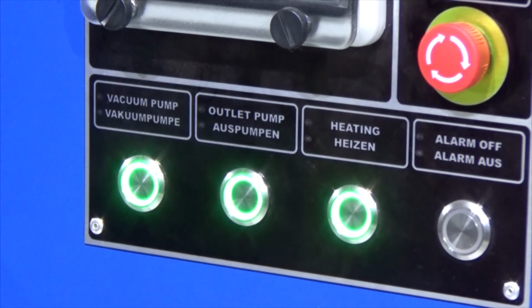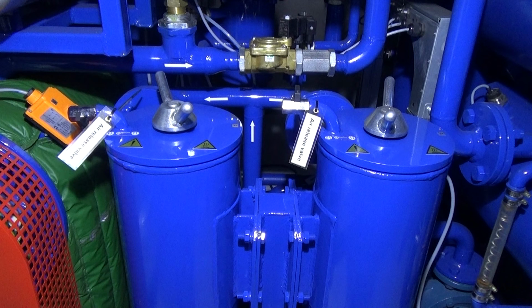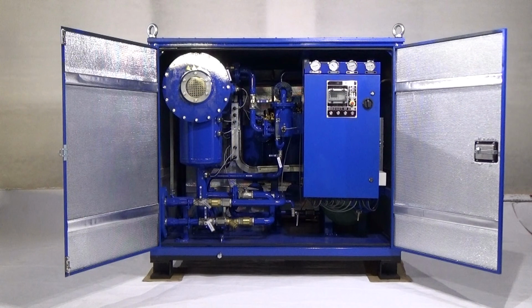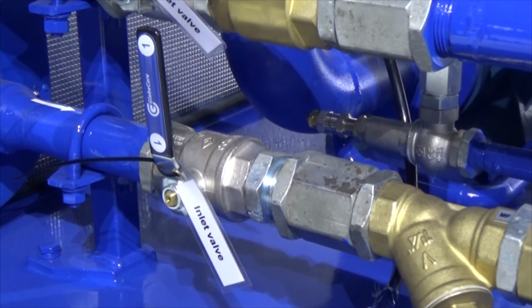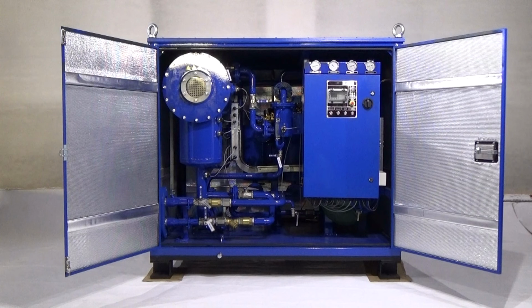When the oil temperature is less than 50 degrees Celsius, bubbles may be observed in the vacuum chamber sight tube. 7. Carefully and partially open air inlet valves MV11 and MV12 on the fine filters. Do not allow oil to splash out. After the filters are filled with oil, close valves MV11 and MV12. 8. When the oil level in the vacuum chamber reaches the mid-level sensor, close valve MV1. The light on the sensor shows that the sensor is engaged. 9. The unit will continue to operate automatically, circulating the oil inside.